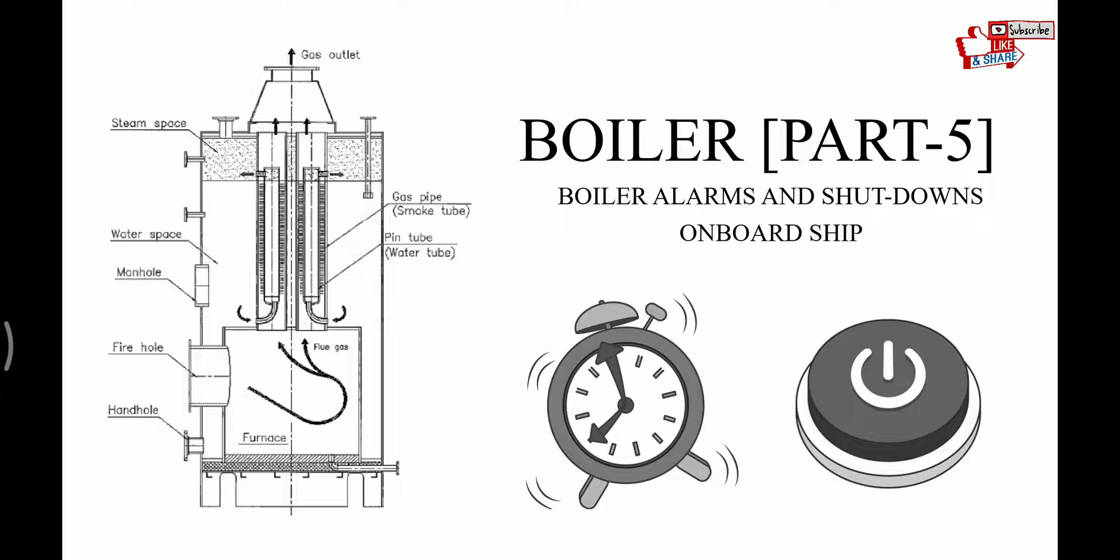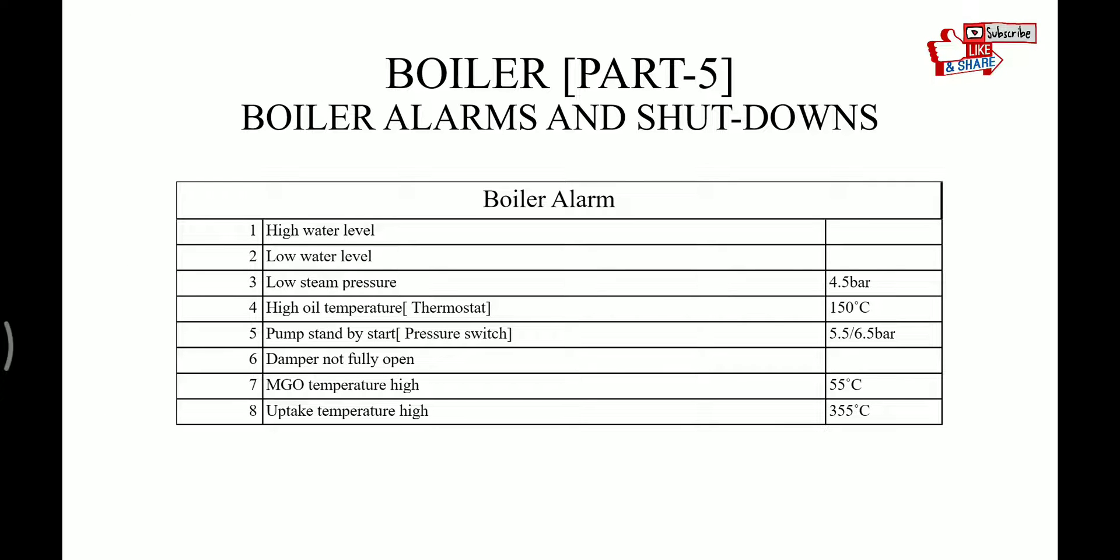I'll request all my friends to help me with your valuable comments below. Let's begin with the alarms on the boiler: high water level, low water level, low steam pressure, high oil temperature from the thermostat, pump standby start from the pressure switch, air damper not fully open, MGO temperature high, and uptake temperature high. The limit values can be seen from the slides.